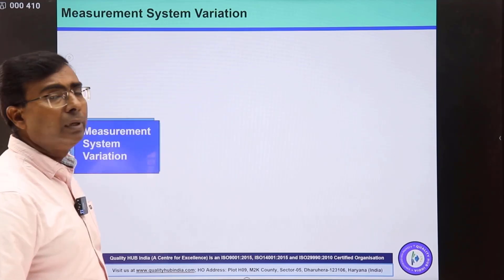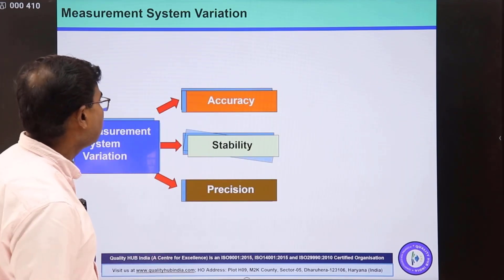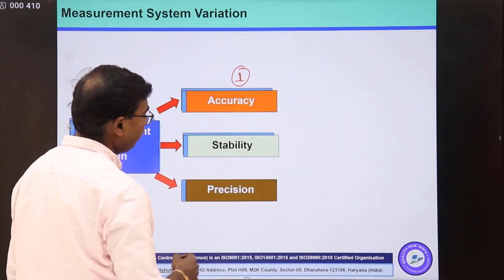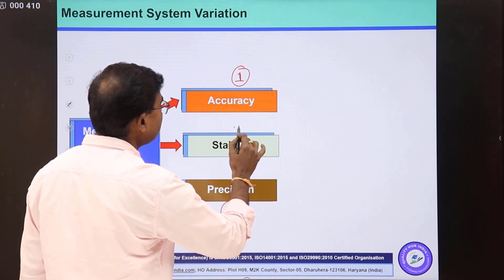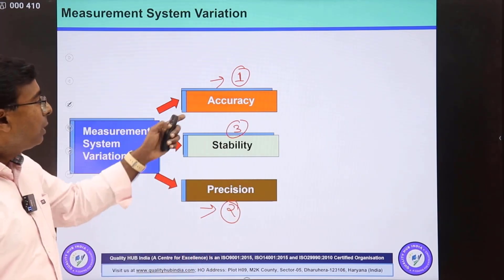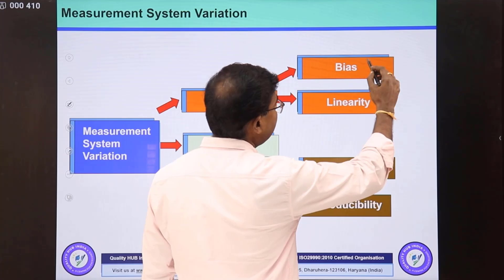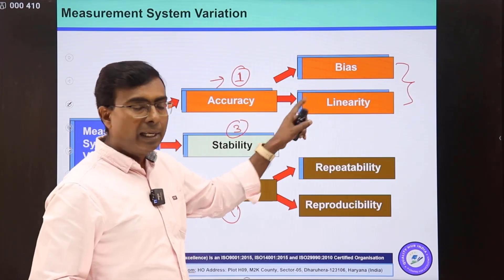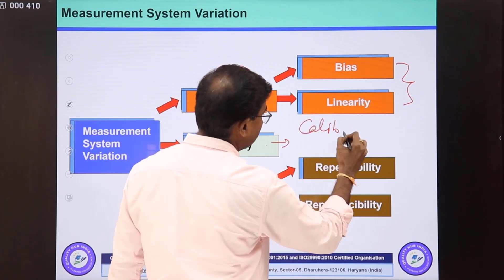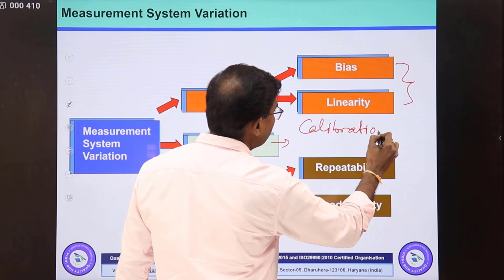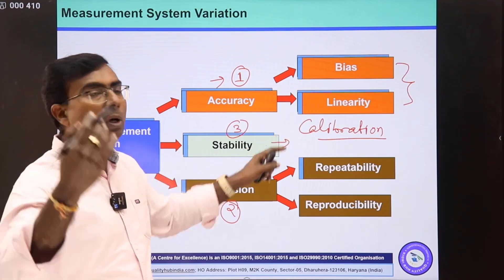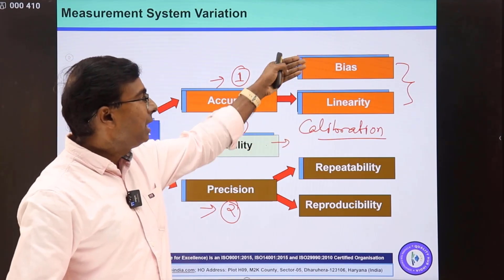What are the types of variation we can have in the measurement system? Measurement system variation can be divided into three categories: the first one is accuracy, the second is precision, and the third is stability. The main components are accuracy and precision. In accuracy, we have bias and linearity. Bias, linearity, and stability are part of your calibration activity. So when you conduct calibration of your instruments or gauges, or send them to an outside lab, they are basically doing a bias study.